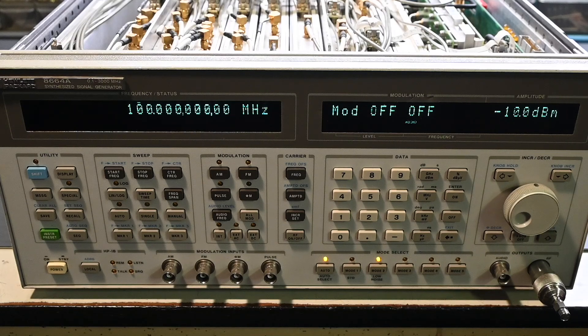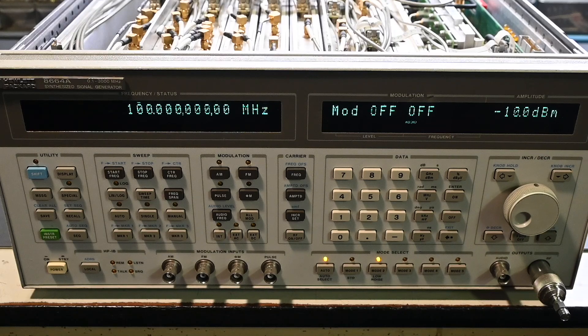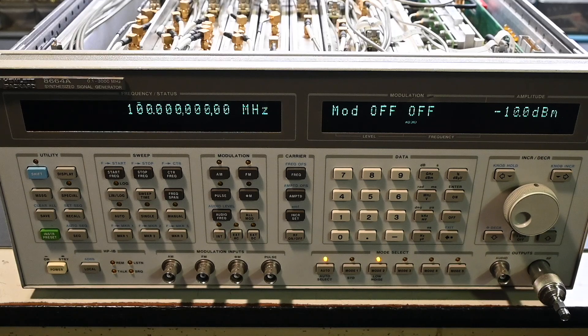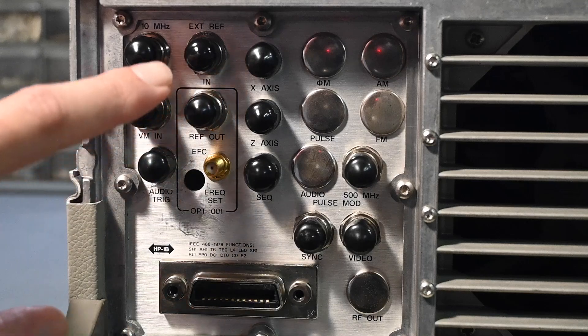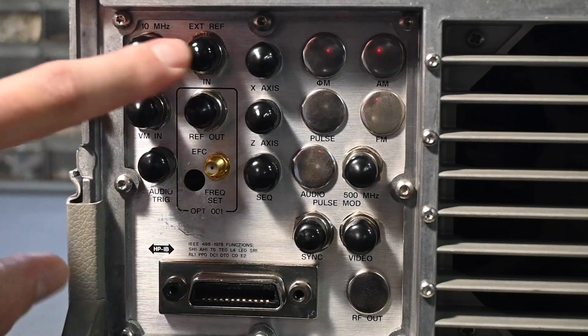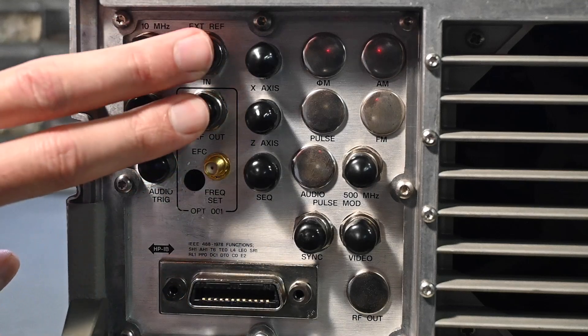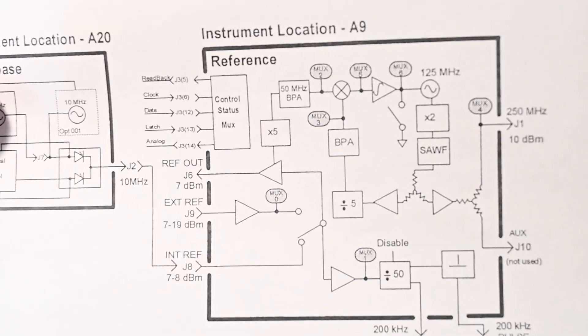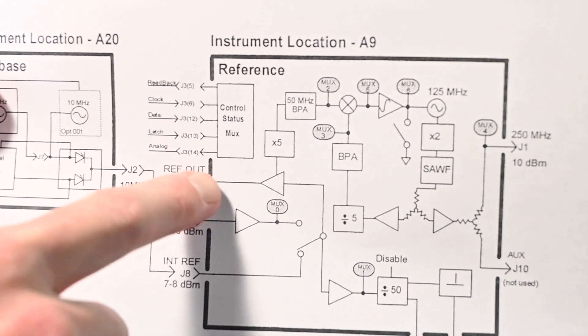So in part one, we saw the output frequency could meet the 10 millihertz resolution, but only after the option one high stability time base was correctly connected. Initially, the rear panel coax jumper was missing, disabling the high stability time base and defaulting back to the standard time base.